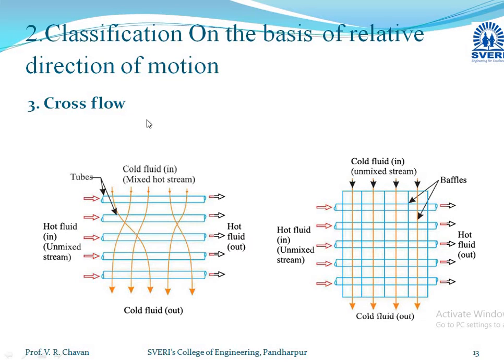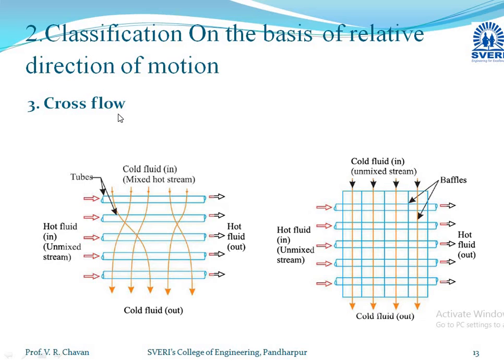The third classification is cross flow. Here, both fluids do not mix with each other — the hot fluid moves through the pipes and the cold fluid moves above those pipes at a right angle. There are two sub-classifications: one where the cold fluid is allowed to mix over the heat exchange surface, and another where the cold fluid streams are kept unmixed and separated over the heating surface. Since the two fluids flow at right angles to each other, it is called a cross flow type heat exchanger.